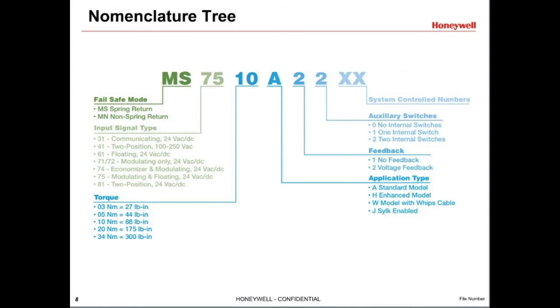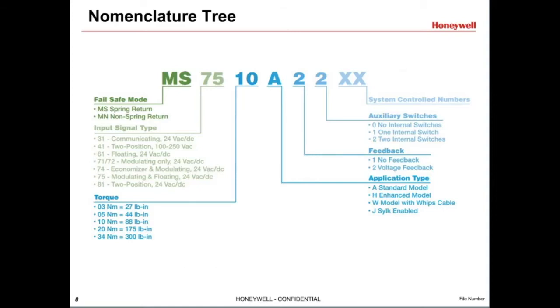The auxiliary switches provide feedback to a controller when the actuator is fully open and fully closed. The first two indicate a voltage feedback that corresponds to the actuator position. The second two indicate an auxiliary switch, which provides a single-pole double throw or single-pole single throw contact closure if the damper is fully open or closed. These switches may be fixed at 7 and 85 degrees or may be adjustable depending on the model number. The last two digits of the part number, the X's here, do not correlate to any specific characteristic of the actuator.